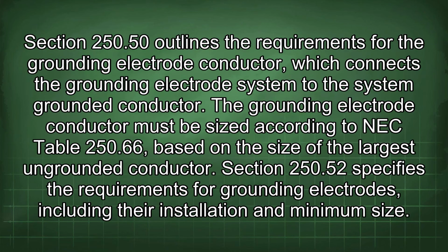Section 250.50 outlines the requirements for the grounding electrode conductor, which connects the grounding electrode system to the system grounded conductor. The grounding electrode conductor must be sized according to NEC Table 250.66, based on the size of the largest ungrounded conductor.